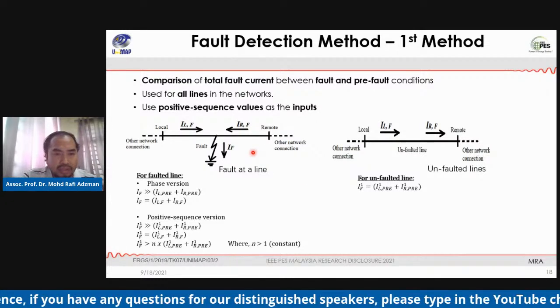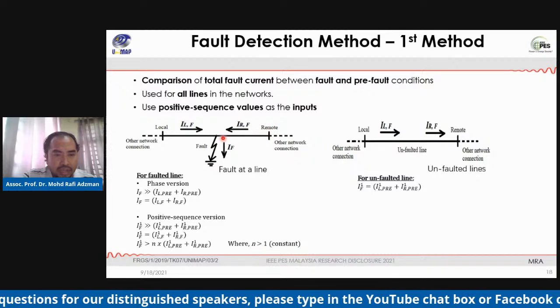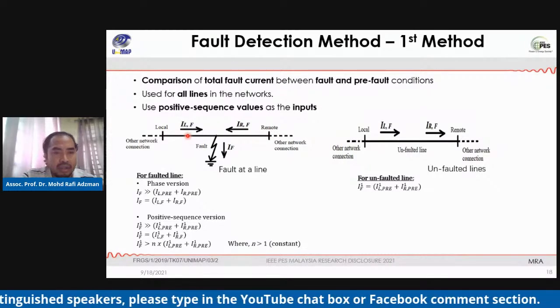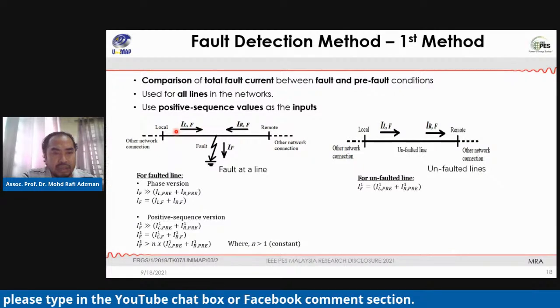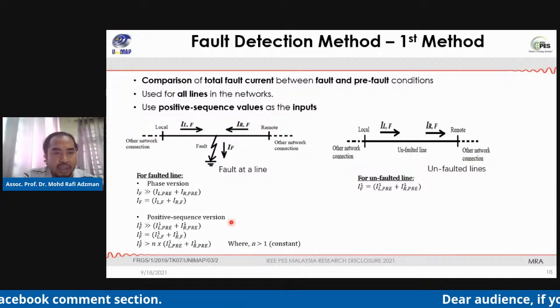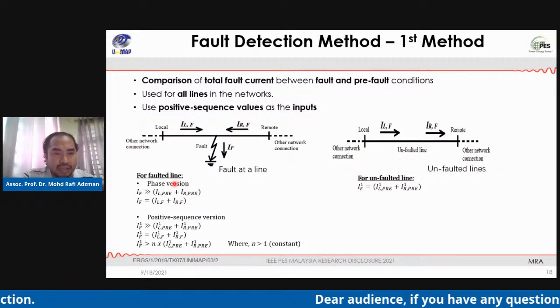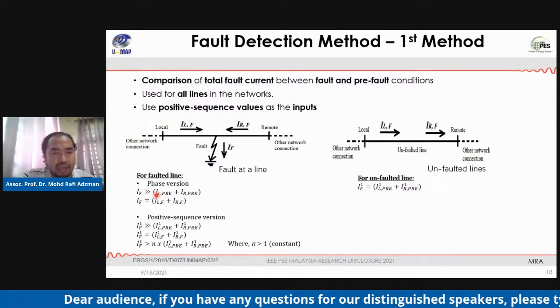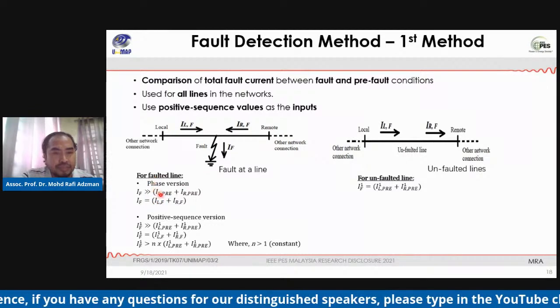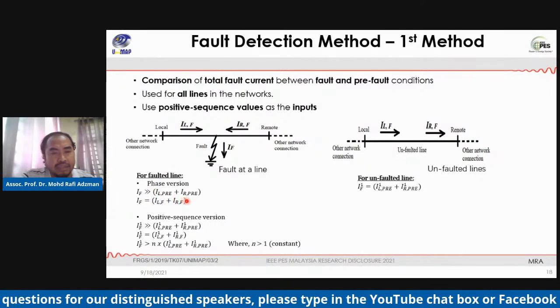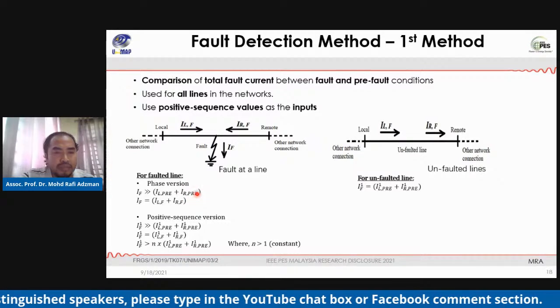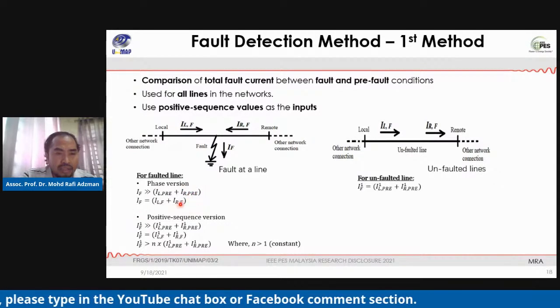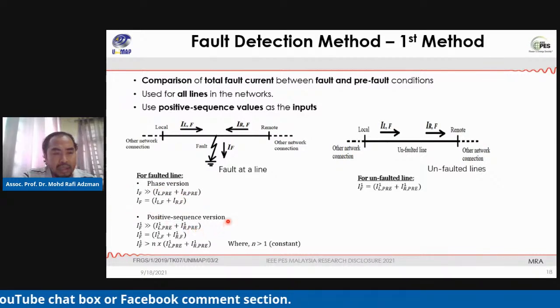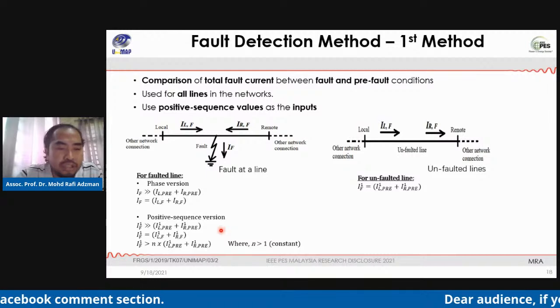For example, in this figure, we have a local and a remote terminal, and we have the local current pre-fault. For example, if a fault happens here, then for the faulted line we have an I fault which is higher than the local current pre-fault plus the remote current pre-fault. This I fault can be calculated using the positive sequence values.